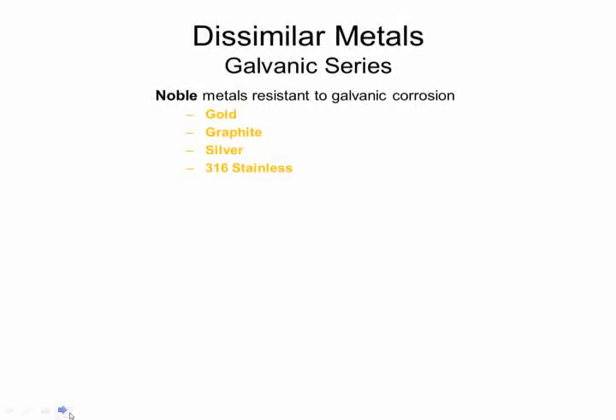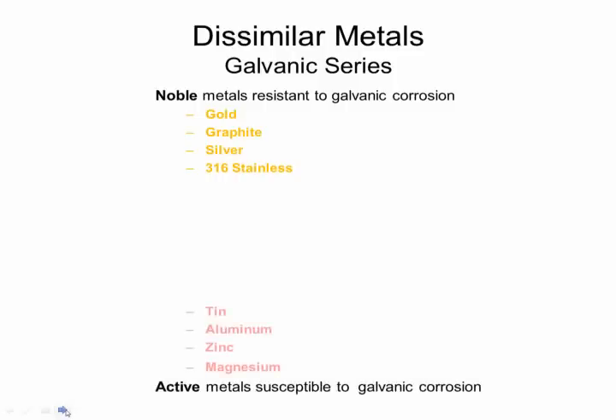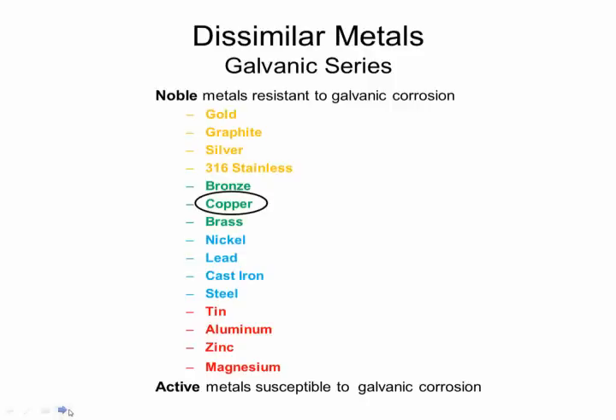Now speaking of the galvanic series, you probably have seen this before, but if you look at the various metals available, starting with your very noble gold, graphite, silver, and then starting to get into metals that you see in hydronic systems, stainless, they're at the top of the chart, very anti-corrosive. And at the bottom of the chart are the metals that are less noble and more susceptible to corrosion: magnesium, tin, zinc, aluminum, etc. And in between are all the other metals that you typically see in a hydronic system. The brass-based alloys of bronze and brass, the copper-based bronze and brass and copper itself, and then filling it out, steel, iron, etc. So the further apart two metals are on this chart, and if they're connected to one another, or by way of another metal still connected, you have the effects of galvanic corrosion that can take place.